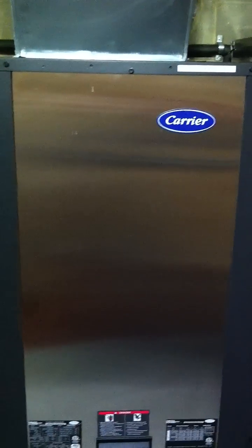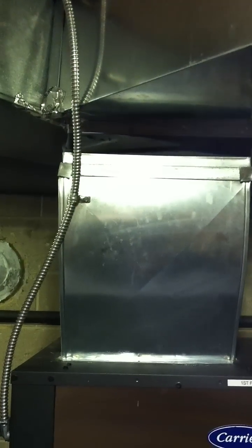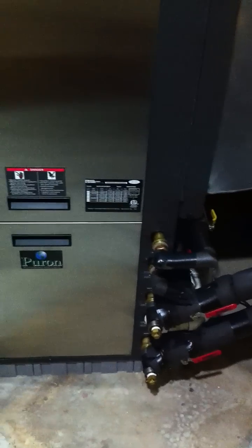The compressor brings it up to the blower area, and then we release that heat off of the refrigerant into the duct system and move the heat into the house. The water circuit has now lost some of its heat and starts coming out of the system at about 40 degrees. So we've now taken five degrees out of the earth in this circuit and are bringing it back out into the field to be regenerated with heat in this continual process.